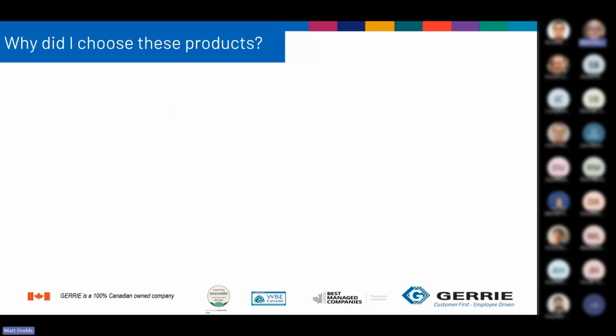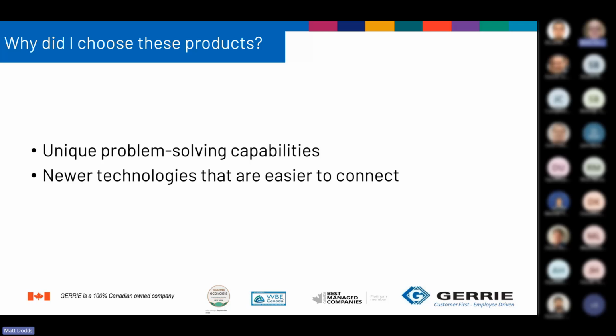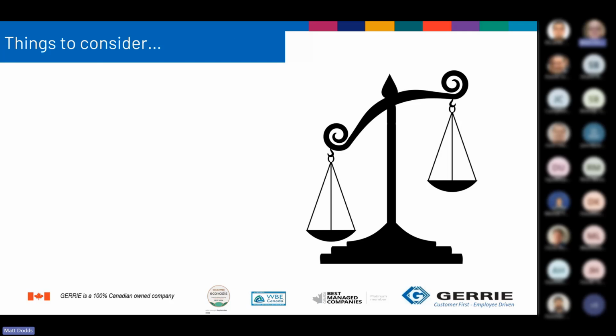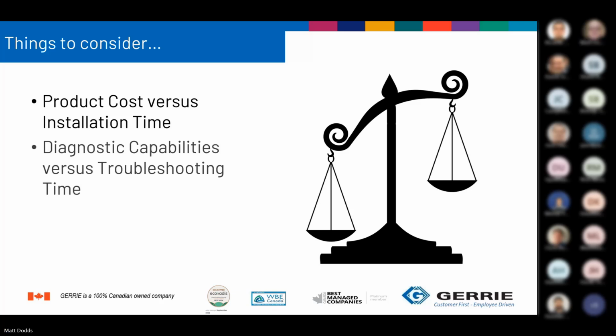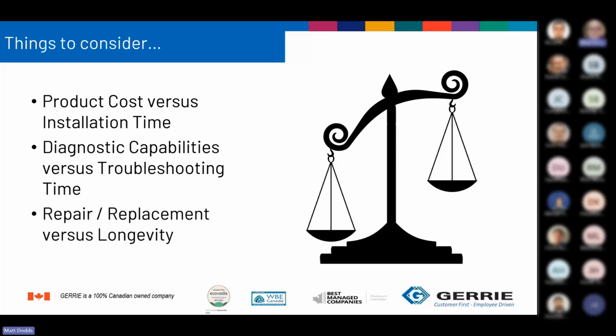So why did I choose these products? Because they offer unique problem-solving capabilities. They are newer technologies that are easier to connect, or they offer better diagnostic capabilities. Some things to consider when selecting a product are the product cost versus installation time. Connectorized solutions minimize the number of connections, leading to reduced panel wiring. No longer do devices need to be hardwired back into an I/O card like they used to. Diagnostic capabilities versus troubleshooting time: products are enabled with all sorts of visual indicators and accessible internal diagnostics and status information. Repair, replacement versus longevity: selecting the right product for the application to survive the environment. So as we continue our journey, I'll point out these things to consider when selecting products and solutions for particular safeguarding needs.